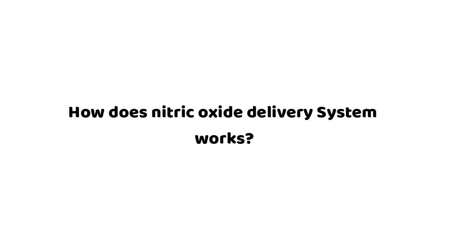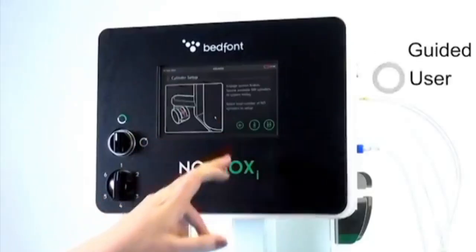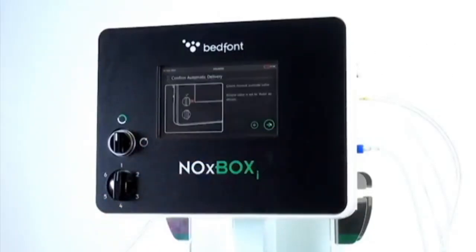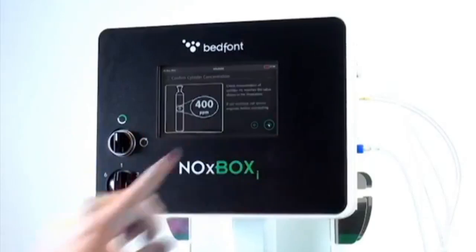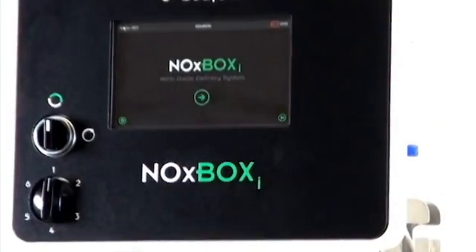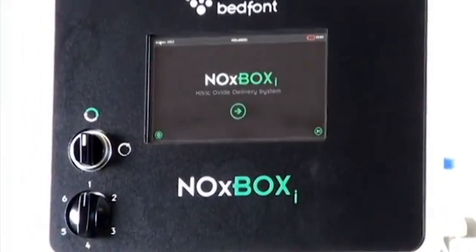How does the nitric oxide delivery system work? A nitric oxide delivery system for adult ventilators has been developed. This is designed to maintain a constant inspired nitric oxide concentration of 16 volumes per million in spite of changes in minute and tidal volumes.